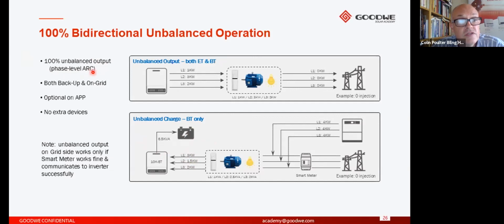Now up here you can see it says 100% unbalanced load, so that means that on one phase we could be supplying absolutely no power at all, but on the other 2 phases we could be supplying the maximum amount on each of those phases. So it's 100% unbalanced. It's achievable on both the backup and the on-grid side, but on the backup side it's default. The configuration of unbalanced load choice is in the app, and there are no extra devices to achieve this. All the equipment comes out of the box, and the app is the only tool you need to configure this system to behave in this fashion. And just a little note here, of course you need to have this all configured and set up correctly for this to actually work properly.